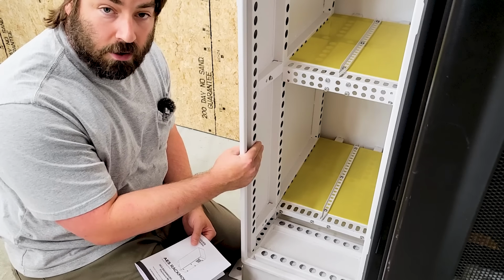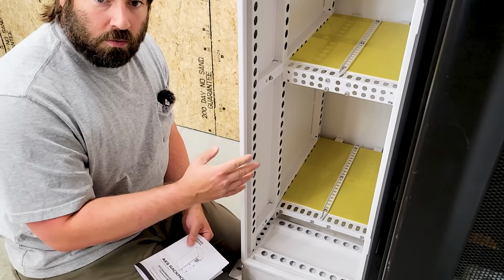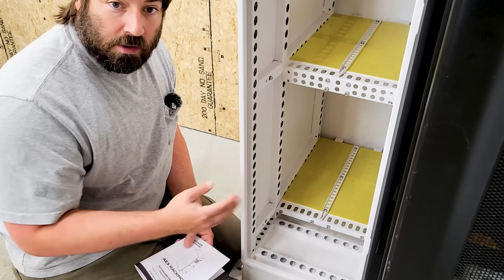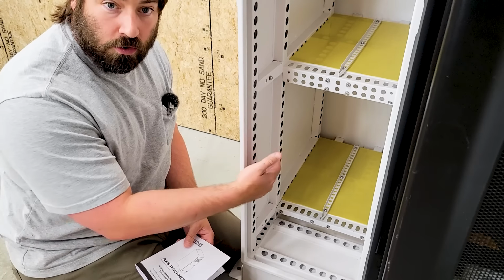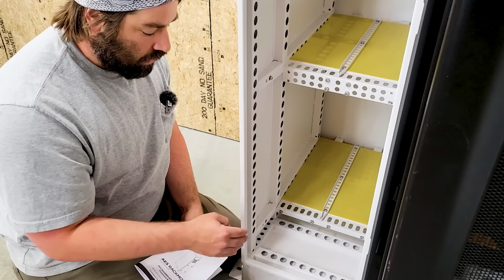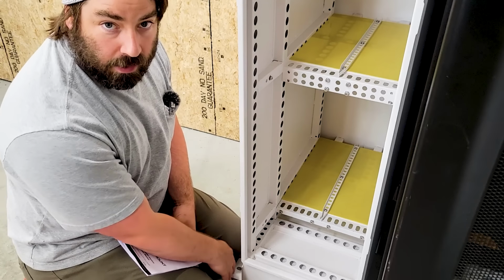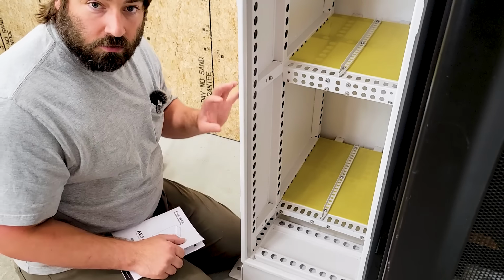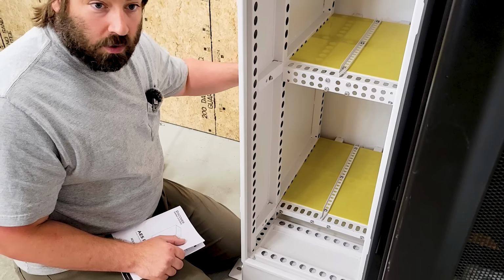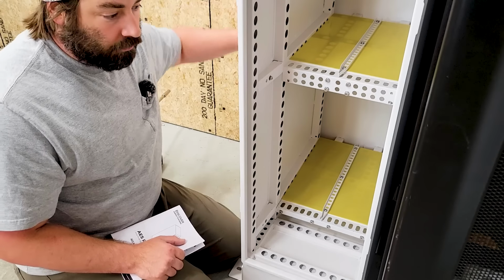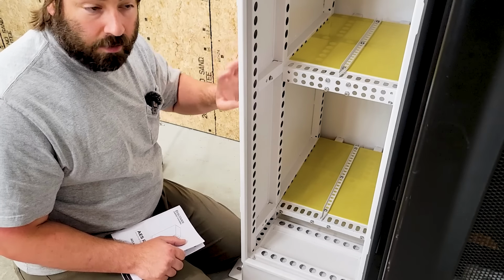So if you're mounting this outside, remember you want to mount it out of the sun. I'm in the northern hemisphere, so I'd put it on the northern side of a building, probably on a concrete pad, anchoring it down. Then you could run watertight conduit back to the building, and you might have several of these lined up going into a building with your inverters. As with most things, there's more than one way to get this done.